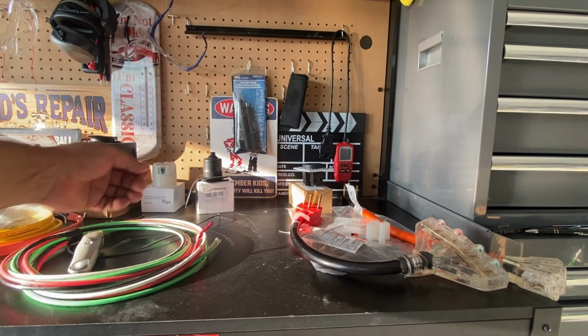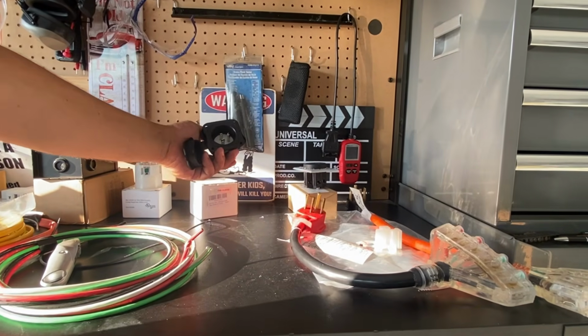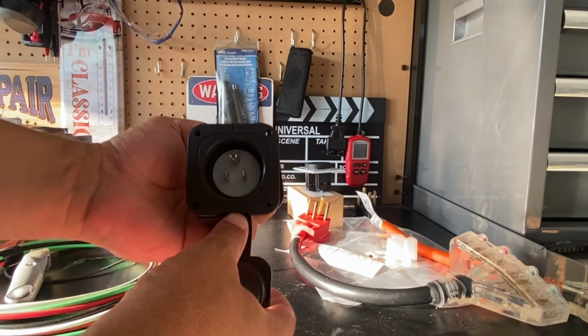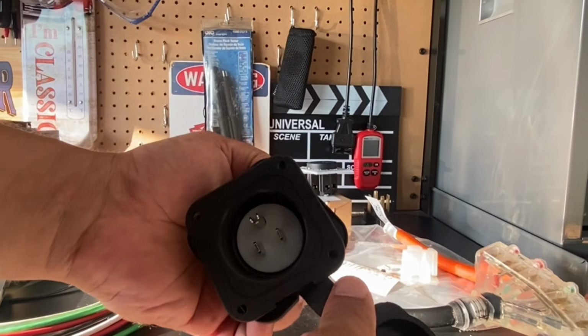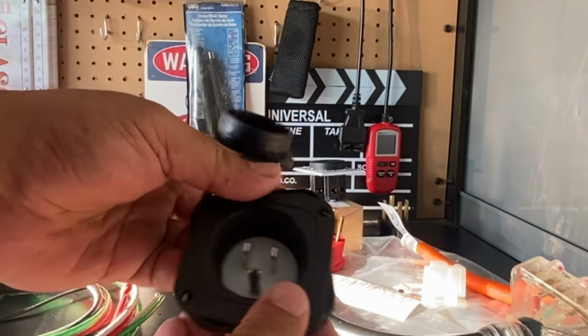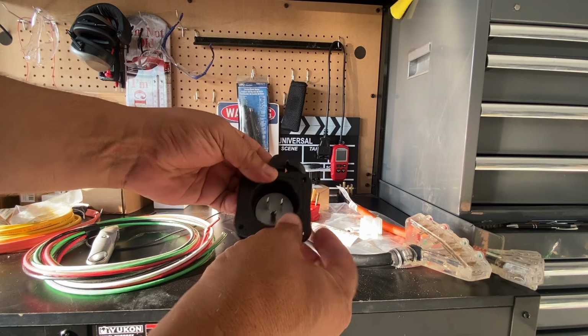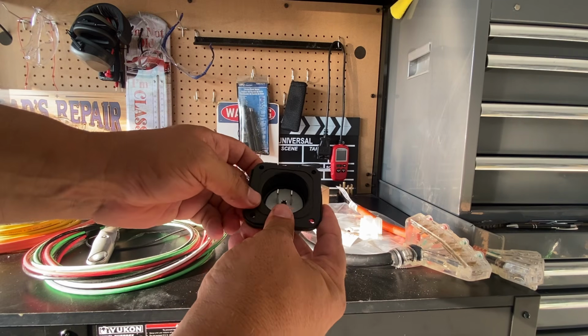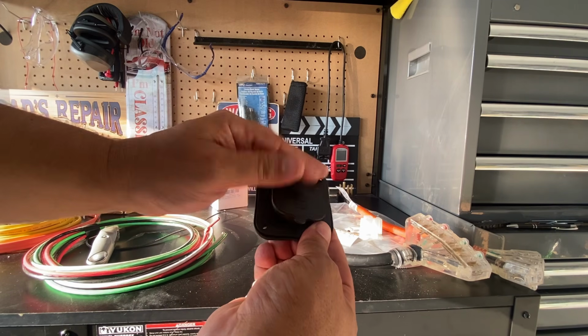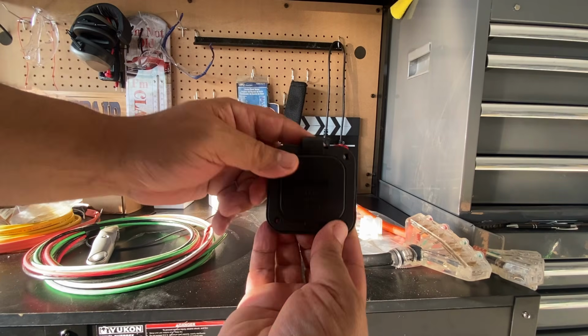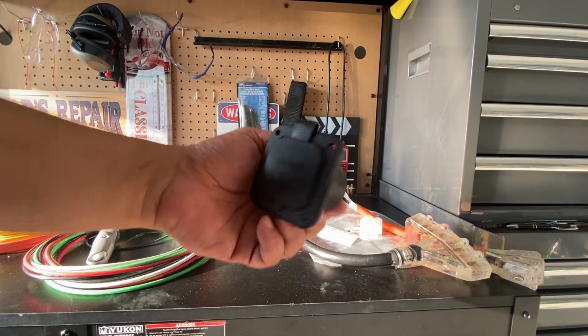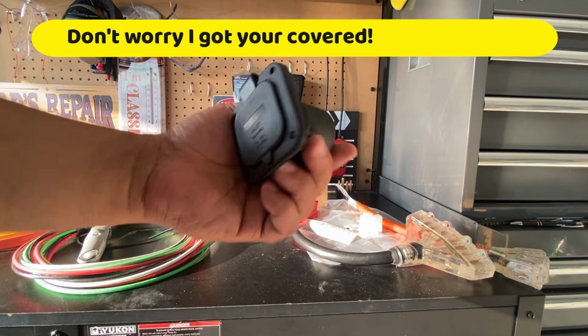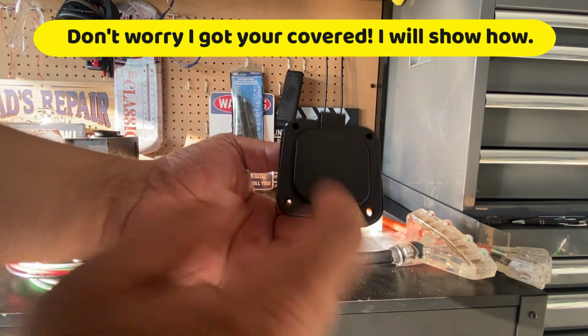As far as home power backup, the easiest way to do it is to use this. However, this will only allow you to get 120 volts into the house. In case of a future upgrade, this is not very good, but it's the easiest. You can use cheaper wiring for this, getting away with 10-2 wire or even 12-2 wire, and it's much cheaper to buy if you want to go this route.